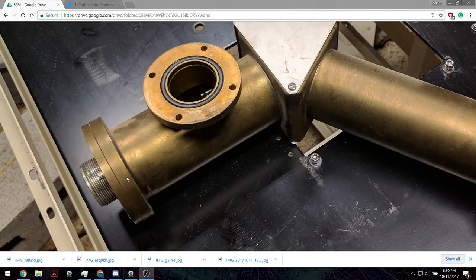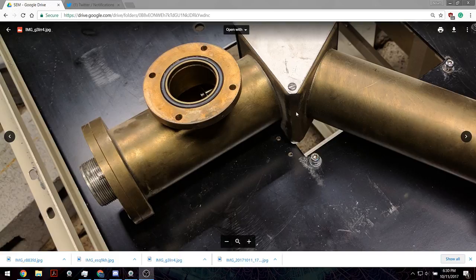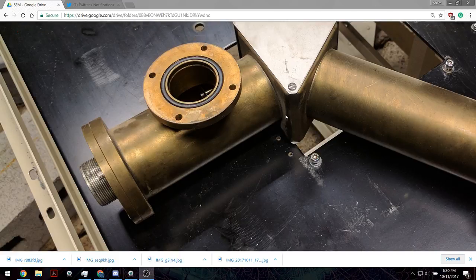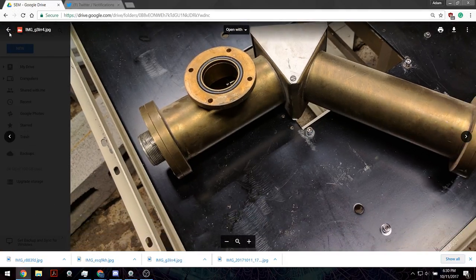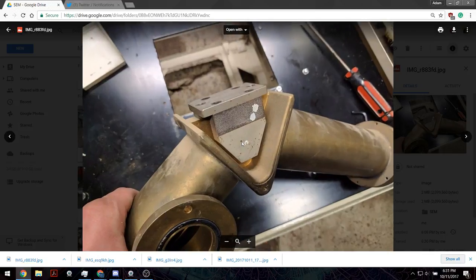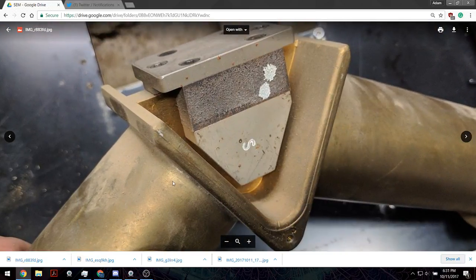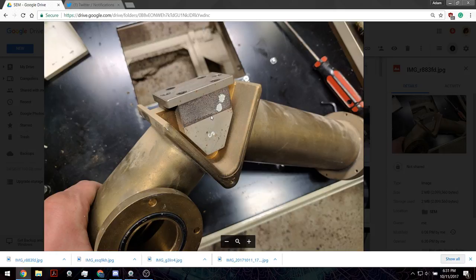And so what happens is the combination of the heater and the high voltage ionizes the gas, so it takes off that electron, so it gives the gas a positive charge. And with that negative high voltage it is accelerated that way down the tube. And as this is accelerated down the tube, it passes by this magnet right there. So that magnet, you can look at it right there, it's called an analysis magnet. And what that does is it's tuned to bend things of a certain mass around this corner. So it's very similar to a mass spectrometer. In fact, it basically is a mass spectrometer.